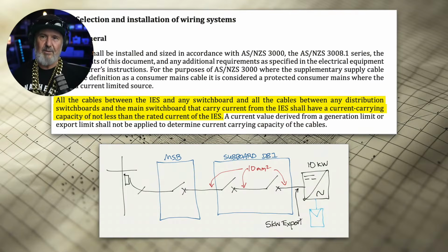That means even though you might have set export limiting, you still have to rate the cable for the maximum possible current. The reason for this is export limiting isn't a magic bullet. It isn't, as it sounds, like a hard limit. It's a soft limit. Basically, the inverter's using usually a power meter or a CT upstream to determine how much current is flowing and will ramp down its output to the target value of export limiting. It doesn't do it instantaneously. And so it is possible to get a brief excessive amount of leakage, you could call it, of exported energy before that export limit's reached.